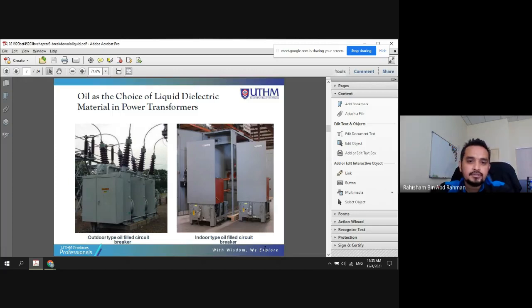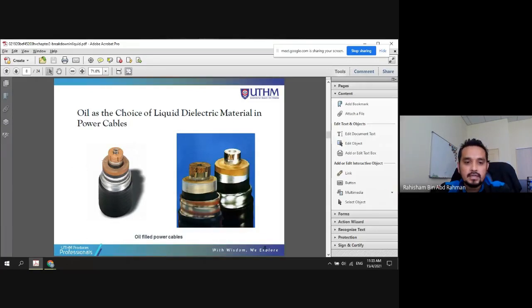Oil is a choice of liquid dielectric for transformers, and we also use oil to wet the insulation paper, then wrap it over the cable. We apply the oil because we want it to fill up the space, fill up the gaps within this insulated paper, so that we can improve the dielectric strength and the capability for this cable to resist current flow.